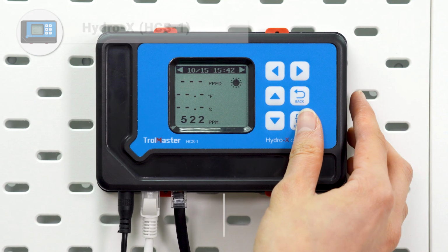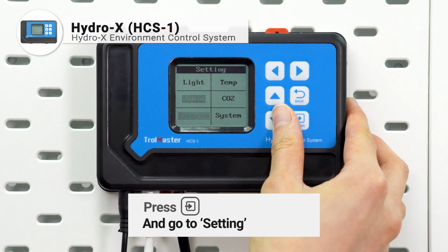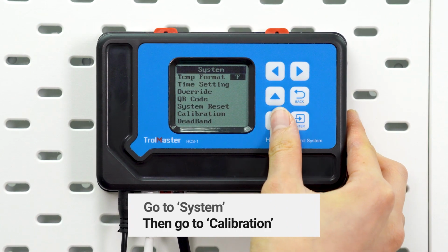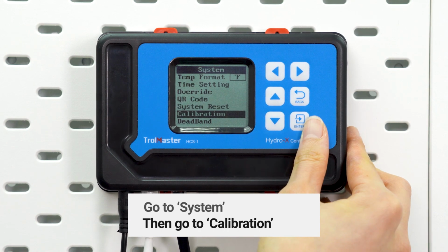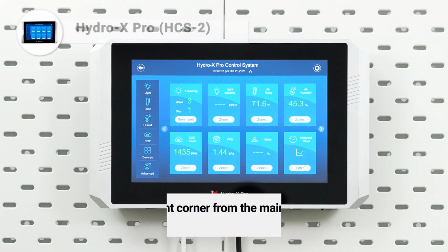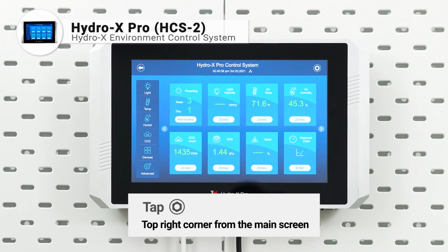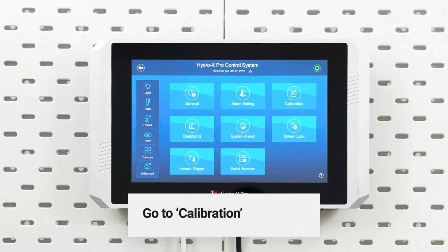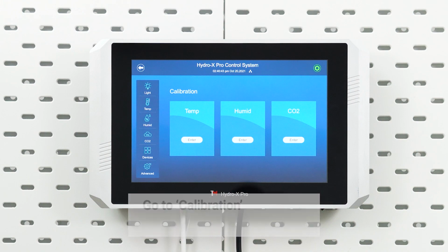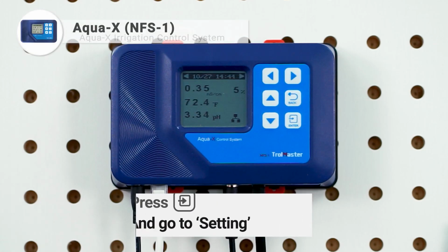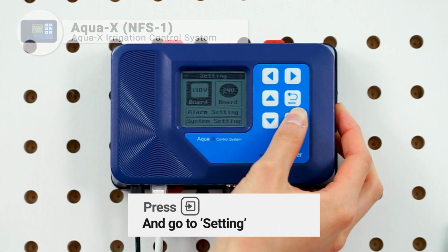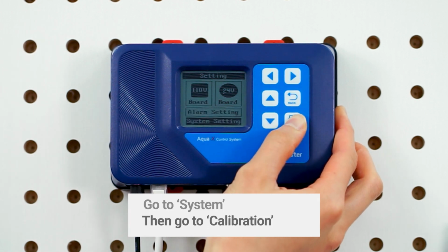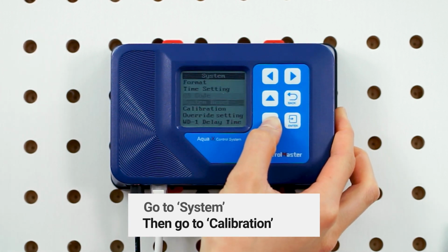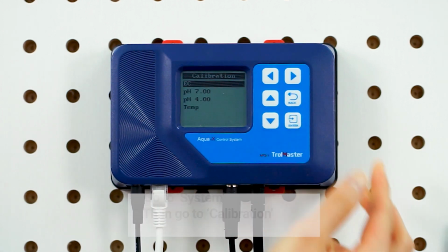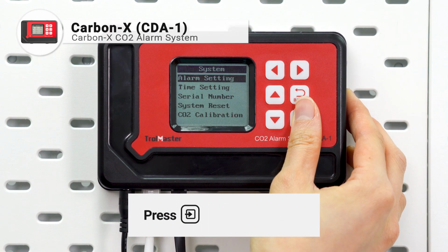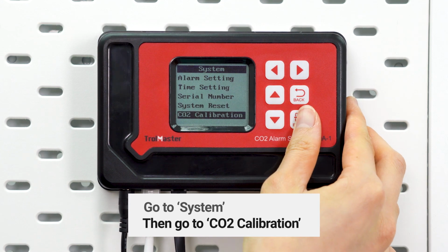If you're using an HCS1 controller, then go to System and Calibration. If it's an HCS2 you're using, just tap the nut icon on the top right corner and pick Calibration. If you have an NFS1, simply press Enter, then go to System Settings and Calibration. Or just press Enter, then go to CO2 calibration if it says CDA1.